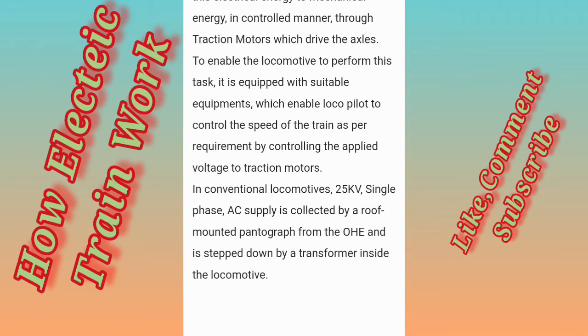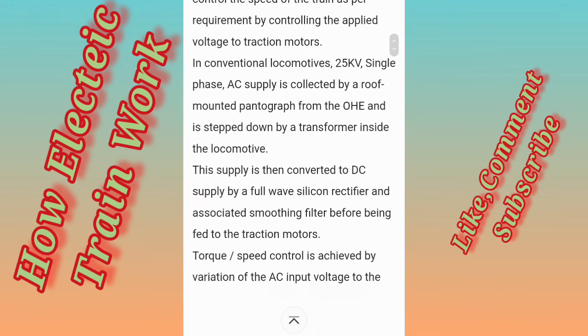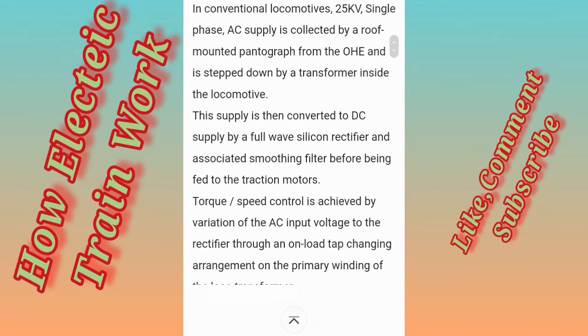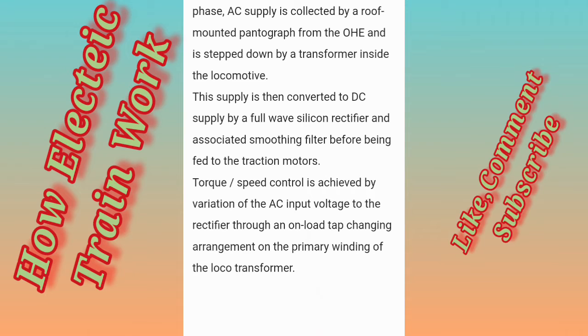In conventional locomotives, 25 kV single phase AC supply is collected by a roof-mounted front pantograph from the OHE and is stepped down by a transformer inside the locomotive. This supply is then converted to DC supply by a full wave silicon rectifier and associated smoothing filter before being fed to the traction motors. Torque and speed control is achieved by variation of the AC input voltage to the rectifier through an on-load tap changing arrangement on the primary winding of the loco transformer.